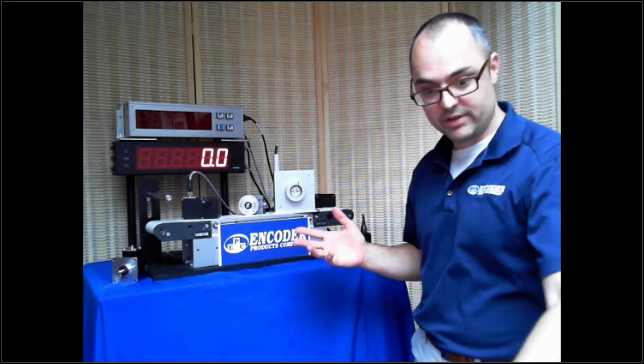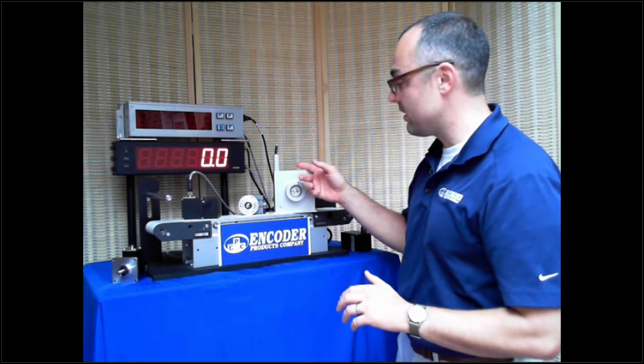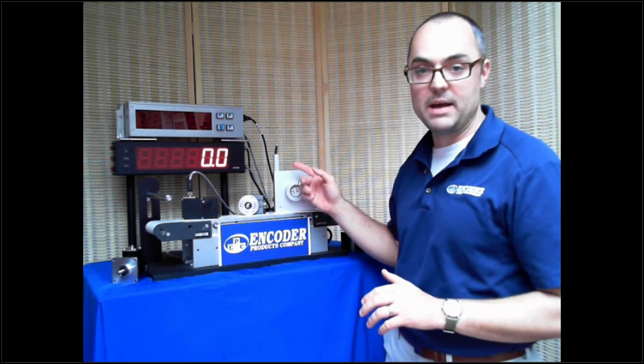The linearity, oh, I wrote a 6 there. What is a 6? Linearity, plus or minus 0.05%. So that linearity is kind of like accuracy. It's your error over the maximum range. So however far I'm going to pull this out, even if I ordered 5 meters, my application is only 3.5. Take 3.5 meters, multiply it by 0.0005, and that's going to be your accuracy over that distance.